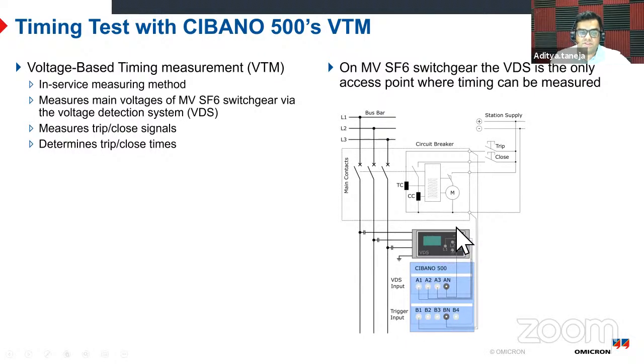So they have a voltage detection system which we can use for measuring the timing of the breaker. We do this test in online condition, because nothing can be done offline unless you do a lot of preparation. The idea is to do non-invasive measurements, very quick and easy. So they have these voltage detection systems which give voltage from capacitors mounted in the bushings on the line side. And we take that signal and see when the voltage dies off. When the voltage is not there, that means the breaker has opened. When the voltage appears again, that means the breaker has made contact. So with this, we can make the measurement.